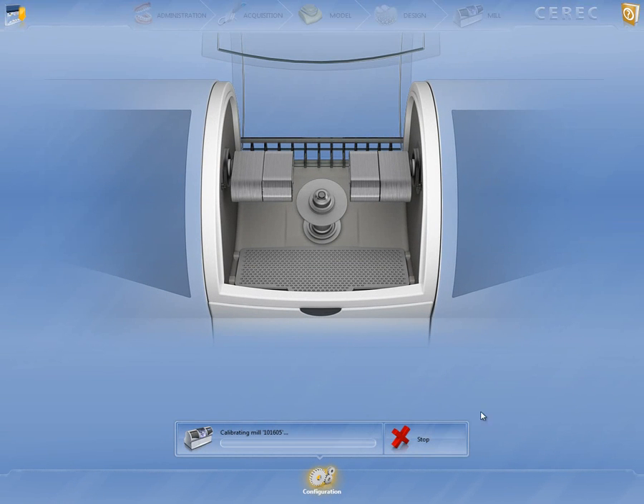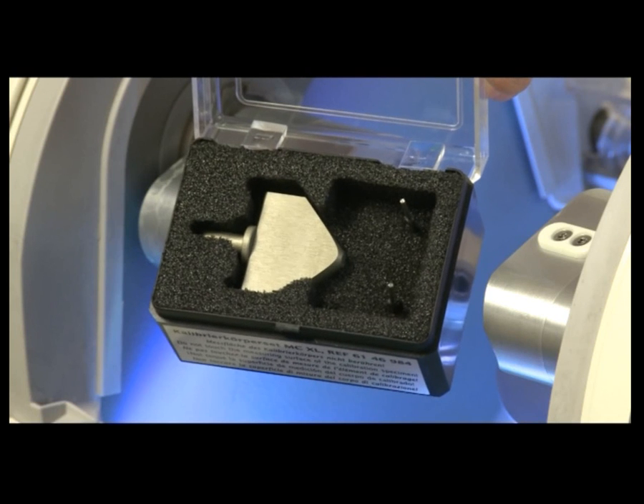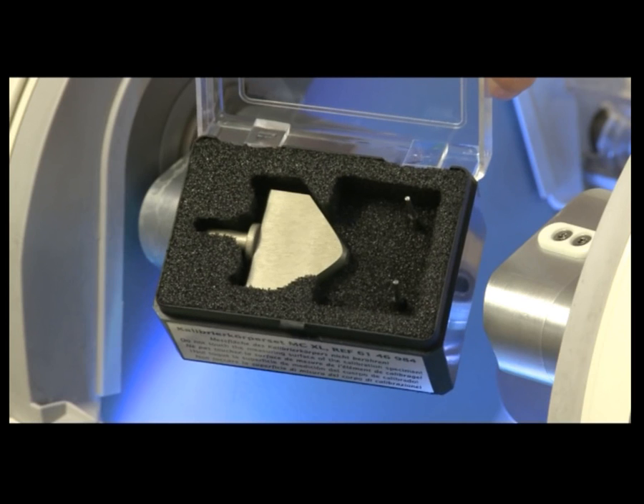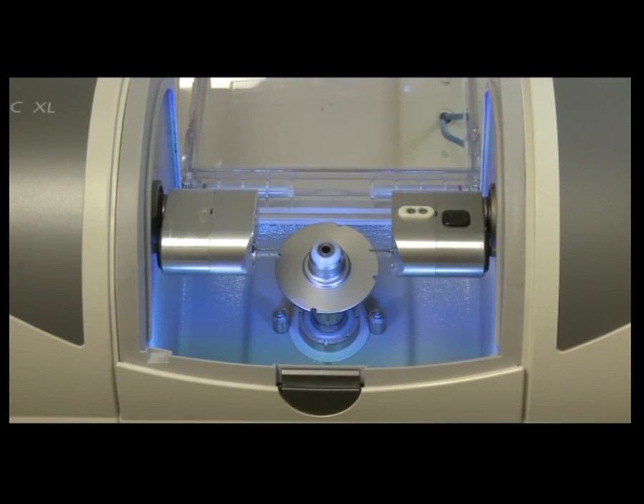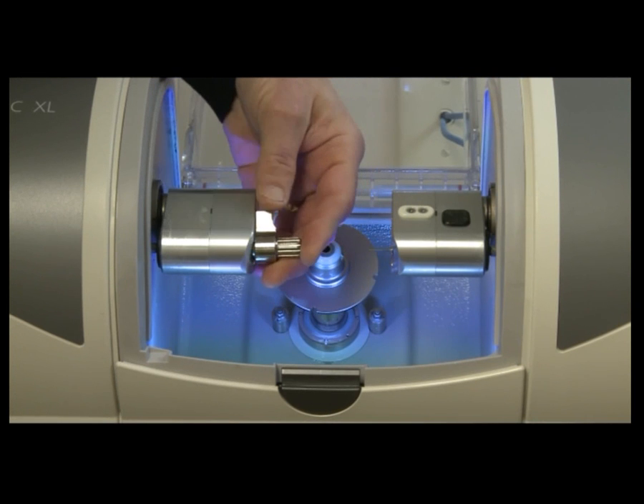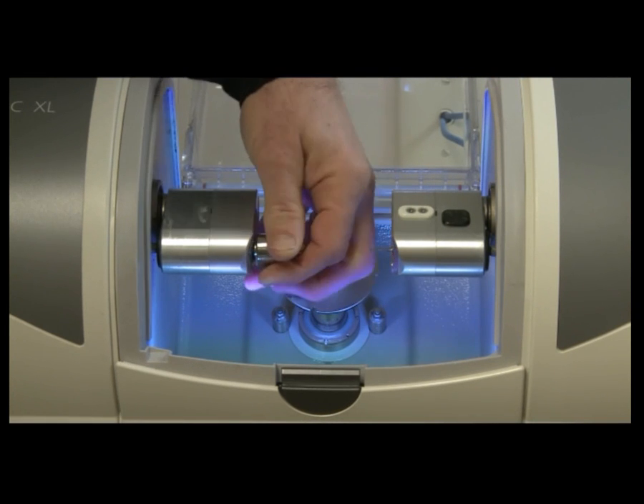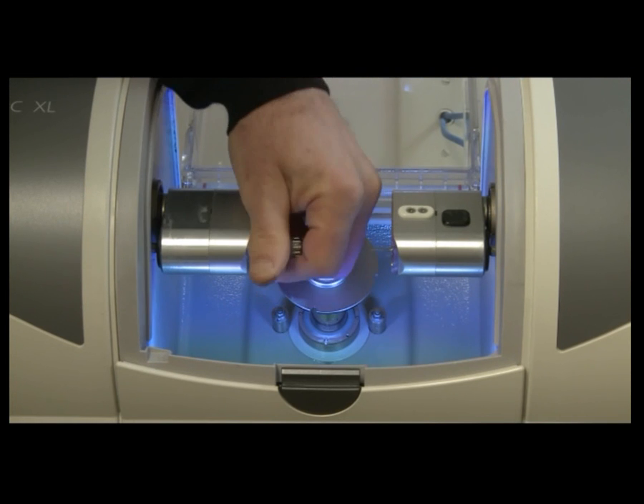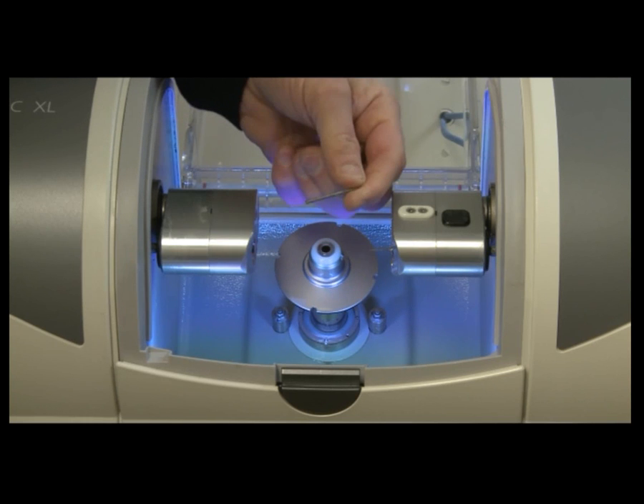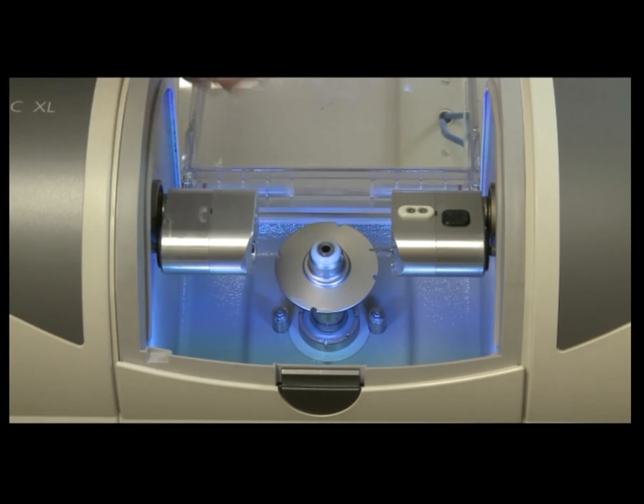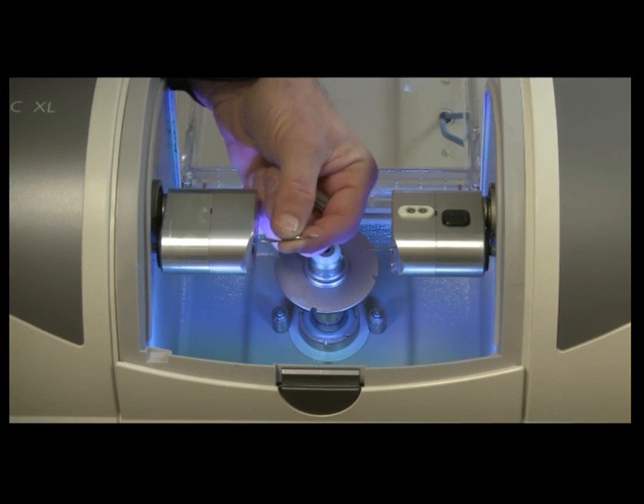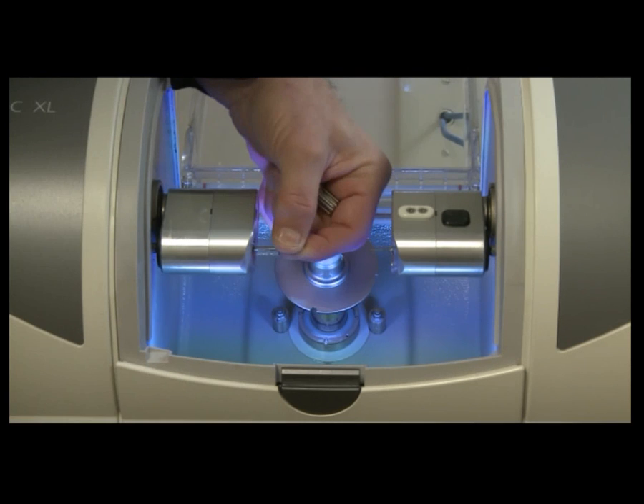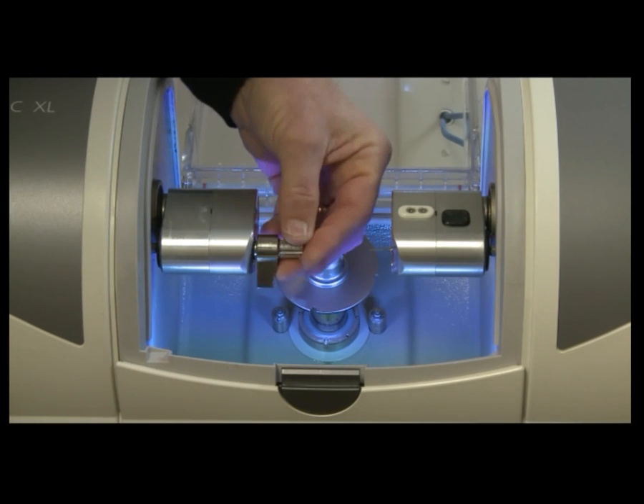You can see it says it's calibrating, and I'm just going to hit the stop button right now. Okay, now we are going to go back to configure. This is your calibration set. You can see it has the pins on the right-hand side and your calibration specimen in the middle. Take your calibration pins. You're going to have to remove the burrs. Remove both the left and the right side. Use your chuck removal or your burr removal tool, which is in the lower left side of your chamber. Turn it to the left and remove a complete chuck and burr. That all comes out, and then you're going to replace it with the specimen or the calibration pins, which do not have any diamond particles on them, so they won't damage your calibration specimen.